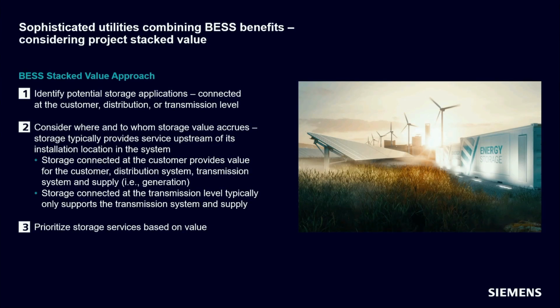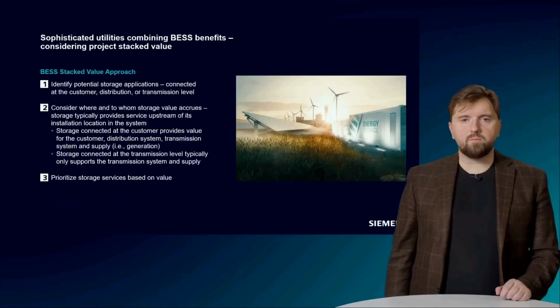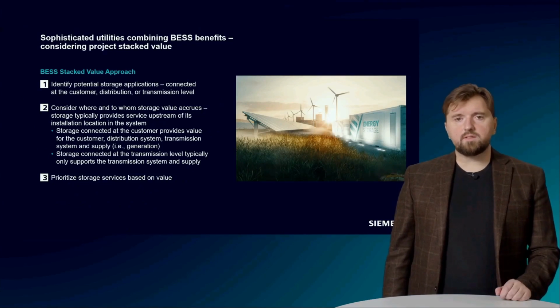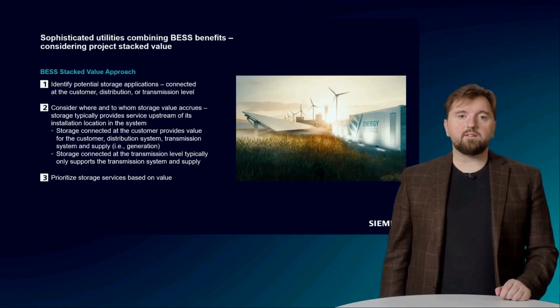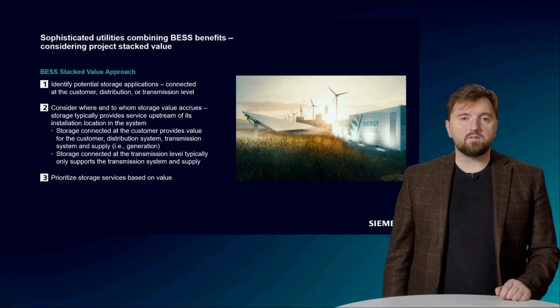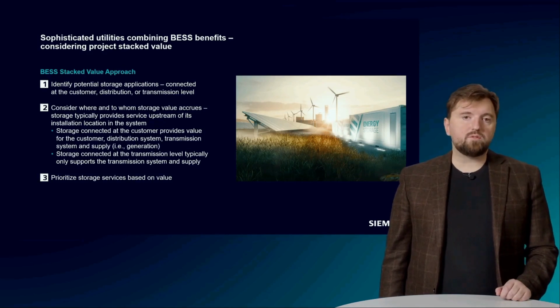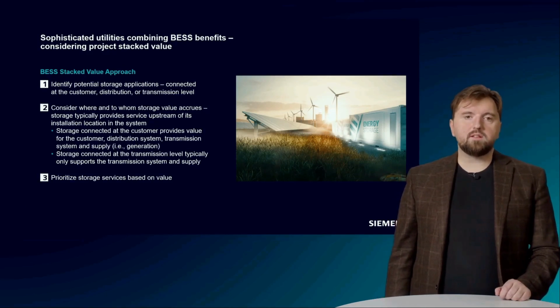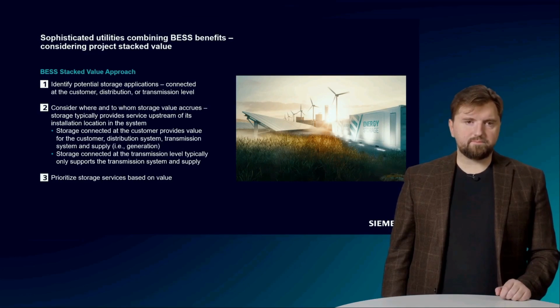For example, a BESS project can help defer the need for a new transmission project by meeting a portion of the peak demand with stored energy during a selected few hours in the year. When not meeting peak demand, the BESS can earn revenue by providing operating reserve services for the transmission system operator. Even though it sounds very nice to have the BESS utilized as much as possible, as we will see in this webinar, value stacking may not really be a choice for some utilities and system operators.